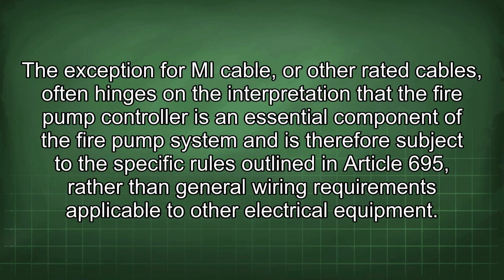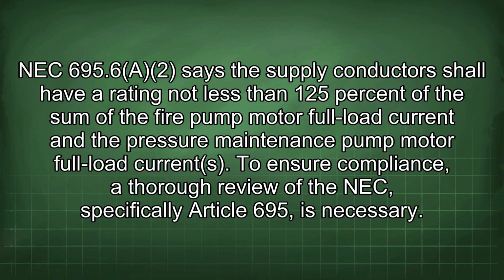The exception for MI cable or other rated cables often hinges on the interpretation that the fire pump controller is an essential component of the fire pump system and is therefore subject to the specific rules outlined in Article 695 rather than general wiring requirements applicable to other electrical equipment. NEC 695.6(A)(2) says the supply conductors shall have a rating not less than 125% of the sum of the fire pump motor full load current and the pressure maintenance pump motor full load currents.